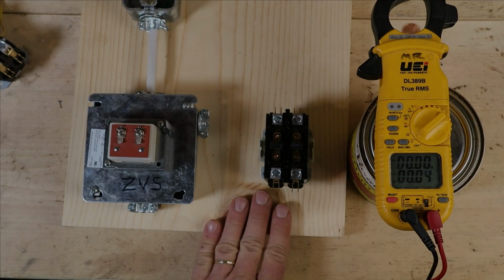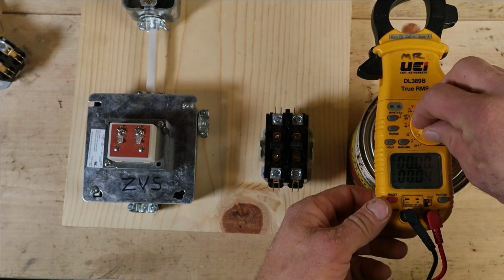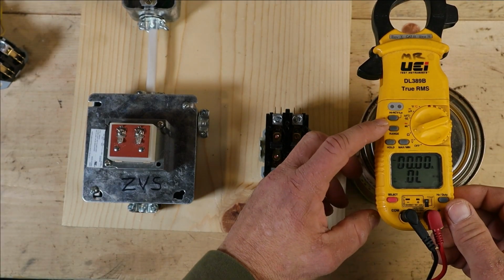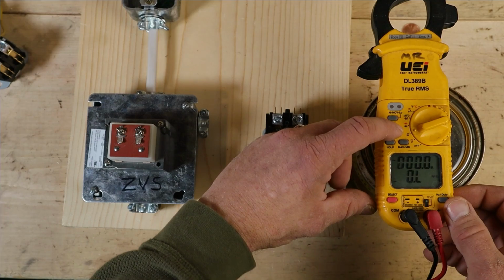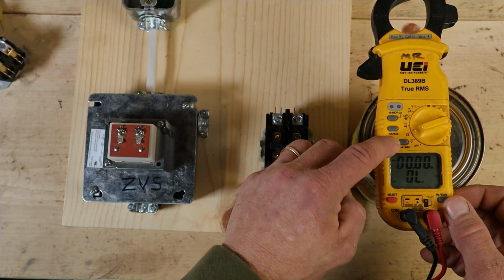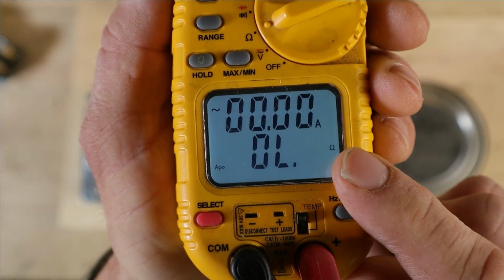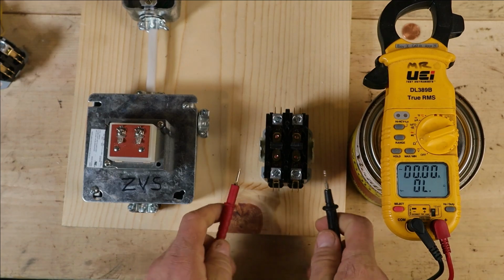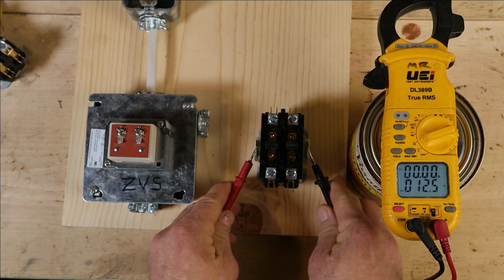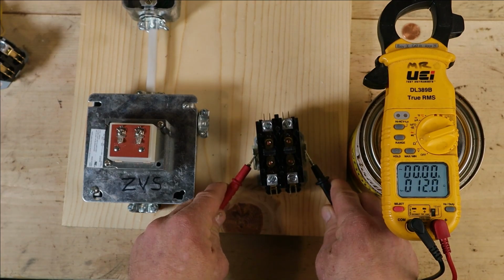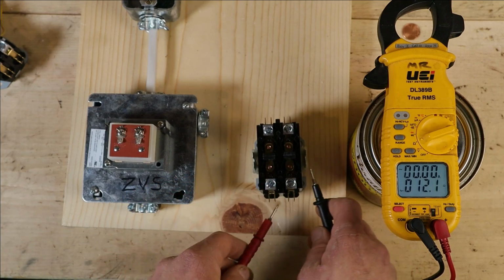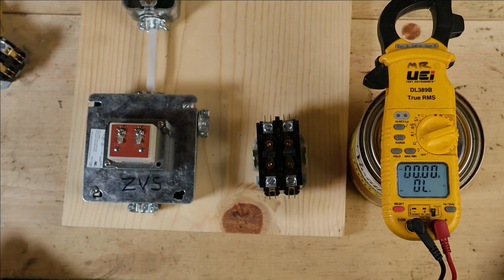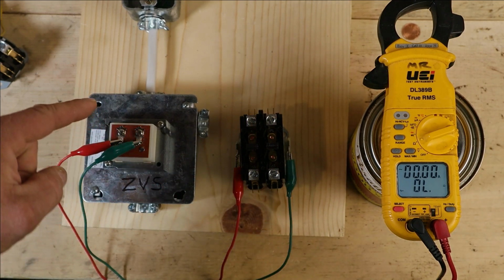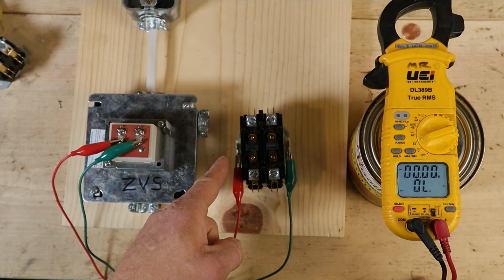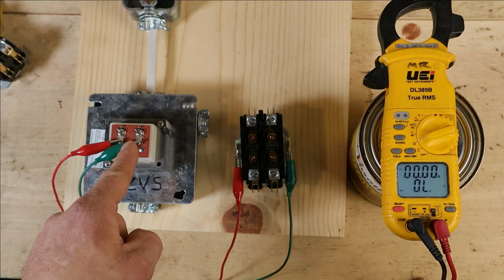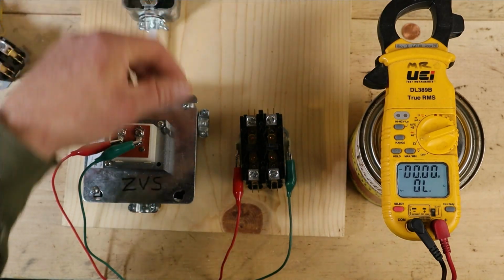Now we're going to do the same thing with a contactor. So I'm going to go back to my ohm readings. I'm going to make sure I'm not in kilo ohms, so I'm just going to go to regular ohms. So you can see I'm in my regular ohm reading there. And when I take a resistance reading across this coil, you can see I'm reading about 12 ohms of resistance. Now let's go ahead and put power to it the same way we did to our resistor. So I got 24 volts coming out to one side of the coil, coming out the other side, back to common on the transformer. Turn the power on.